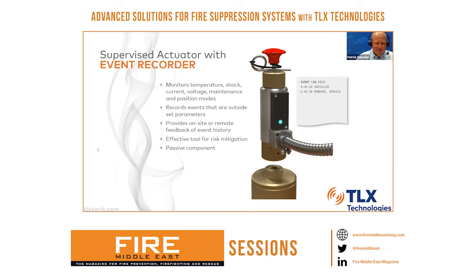We typically call it, by nickname, a black box. You can see it on the side of the unit, but really what it does is we have the ability to monitor temperature, shock, current, voltage, and also the position modes that we mentioned earlier with regards to the installation supervision and the pin state position. On the electronics of the board itself, we have a 3-axis accelerometer that can detect impact loads in those 3 axes. And so between monitoring the voltage and current inputs and those shock loads, we can determine when the device has fired, whether it was mechanically actuated or electrically actuated, and it will create this event log.